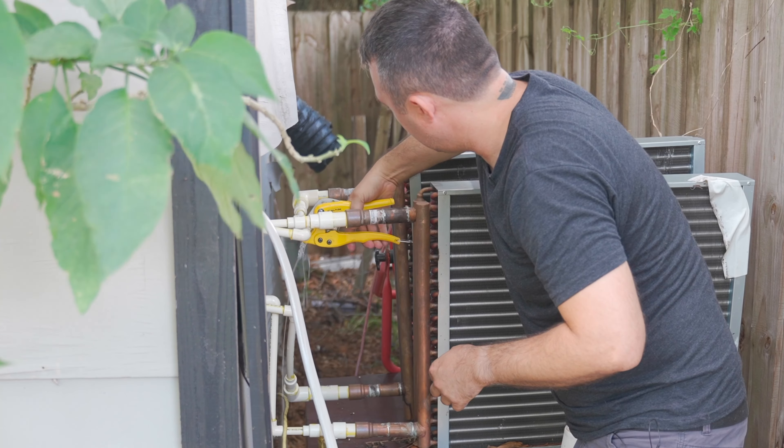I forgot to put a T-valve anywhere in this thing. The liquid won't make its way down in and through here — the pump only goes one way. Without a T-valve in here, this can't fill up; it stays full of air and the pump can't prime. I need to cut one in, but as soon as I cut this, that's going to allow air in, which means all this dielectric fluid is going to try to push through there and squirt out the top. So I've got to glue this up, cut this pipe, and try to put it all together before the dielectric fluid makes it there, then hope the glue can just do its thing.